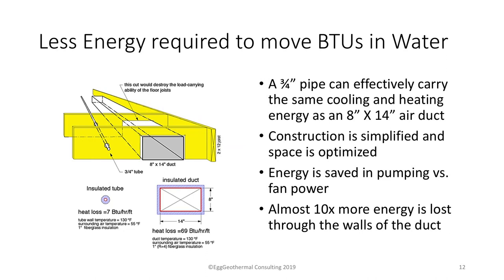There are two fundamental ways to move energy through a building: a forced air duct system or a hydronic pipe filled with water. An 8-by-14 duct moves as much energy as a 3/4-inch pipe. Hydronics are more efficient — in that pipe you lose 7 BTUs per foot per hour, while in that duct you lose ten times that amount. For larger systems like a school, it's much more efficient to distribute energy through a hydronic pipe than through ductwork.